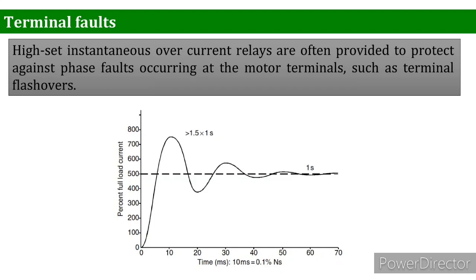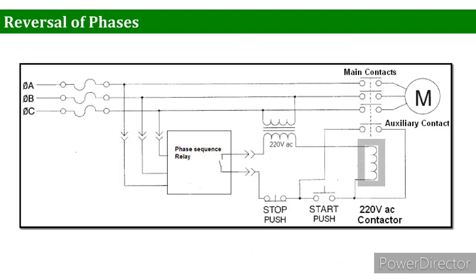it will go back to normal. Now we have the reversal of phases. When there is a reversal of phase sequence, the motor rotates in a direction opposite to its normal direction of rotation. In several applications such as elevators or hoists, this is a serious hazard. In such a situation, a phase sequence detector, which is generally a part of the under voltage or over voltage protection scheme, can be used.